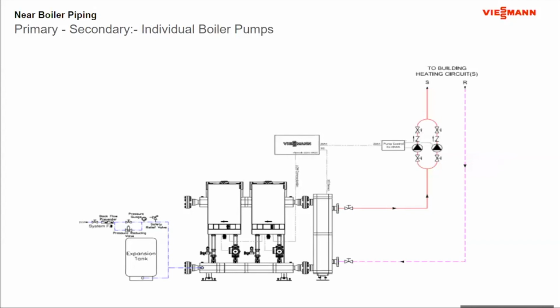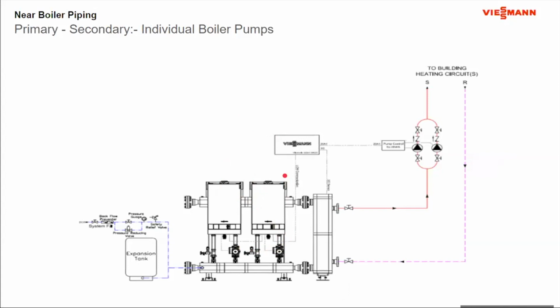Now, here's another example showing the boiler pumps. I wanted to throw that out here again. We talked a little bit about this earlier. So if I'm doing wall hung boilers, here are my boiler pumps off of a manifold. So again, it's primary, secondary, individual pumps, pump size for the specific requirement of the boiler, and it's just for a single boiler. And then the pump starts when the boiler is enabled.